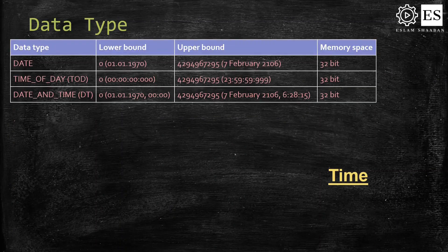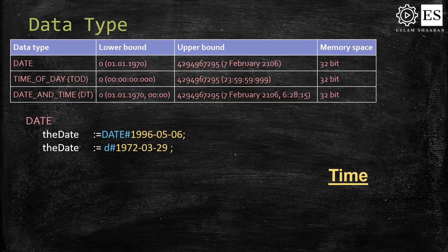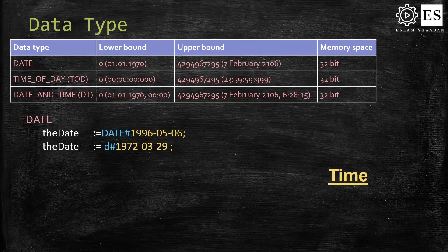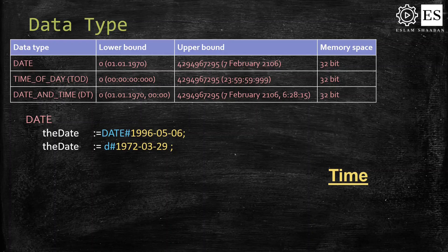In some applications it is more convenient to represent time in the PLC program as we represent it in our daily activities as humans, by using the DATE, TIME_OF_DAY, or DATE_AND_TIME data types. The DATE data type, as the name implies, lets you specify dates. When setting a value to a DATE variable, you write D or DATE followed by a hashtag and then the value. The date declaration must be specified in the format year-month-day. Internally TwinCAT treats date values like DOUBLE WORD — the time is specified in seconds from the 1st of January 1970.